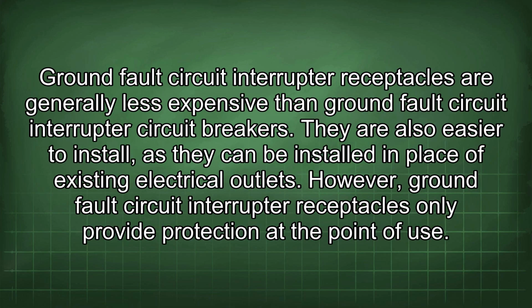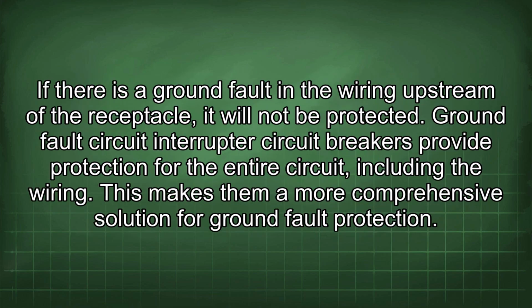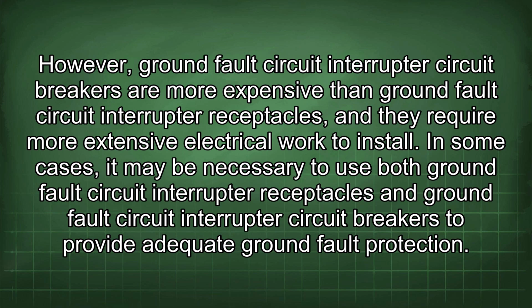Ground fault circuit interrupter receptacles are generally less expensive than ground fault circuit interrupter circuit breakers. They are also easier to install, as they can be installed in place of existing electrical outlets. However, ground fault circuit interrupter receptacles only provide protection at the point of use. If there is a ground fault in the wiring upstream of the receptacle, it will not be protected. Ground fault circuit interrupter circuit breakers provide protection for the entire circuit, including the wiring. This makes them a more comprehensive solution for ground fault protection. However, ground fault circuit interrupter circuit breakers are more expensive than ground fault circuit interrupter receptacles, and they require more extensive electrical work to install.